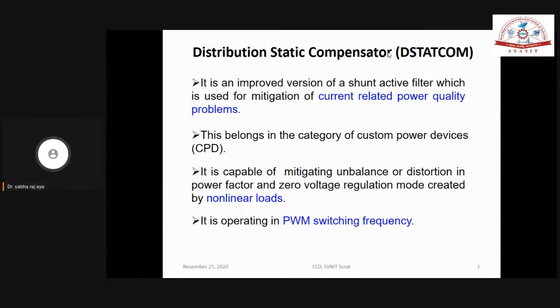Okay, means the D-STATCOM was basically designed for compensation of reactive power. For compensation of reactive power, people designed the D-STATCOM. But additional features are harmonic compensation and unbalancing. If the load is unbalanced, this is going to maintain supply side balanced sinusoidal current. This is not going to do anything towards the voltage side. This is one thing.